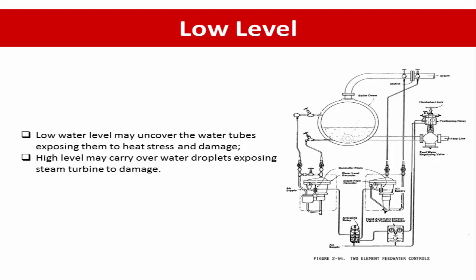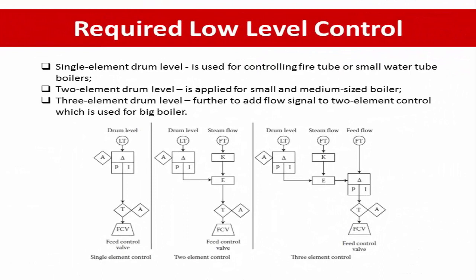In engineering practice, there are many control configurations to maintain the water level. Single element drum level control is a simple type used for controlling fire tube and small water tube boilers, based only on the boiler level without compensation. Two element drum level control is applied for small and medium size boilers, measuring steam flow along with boiler drum level using steam flow feed-forward control. Three element drum level control further adds a feed water flow signal, and is most widely used for large boiler capacity.